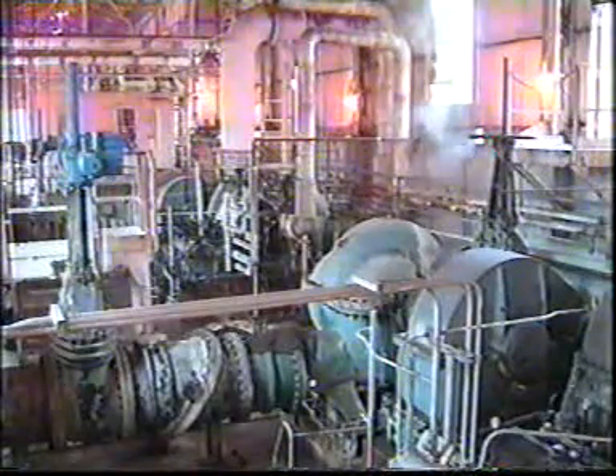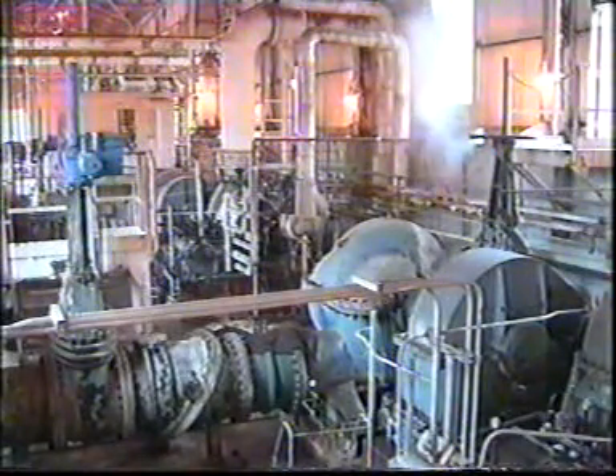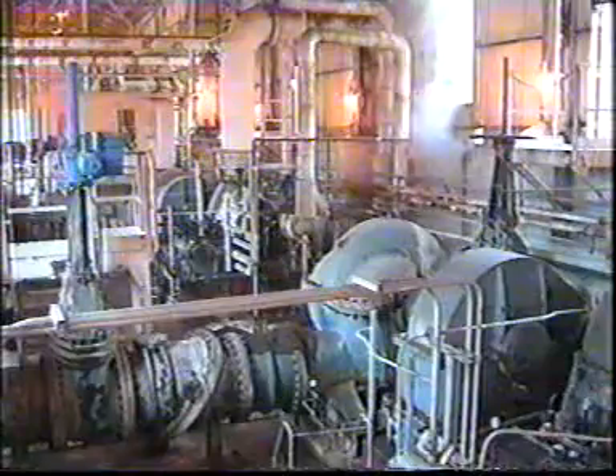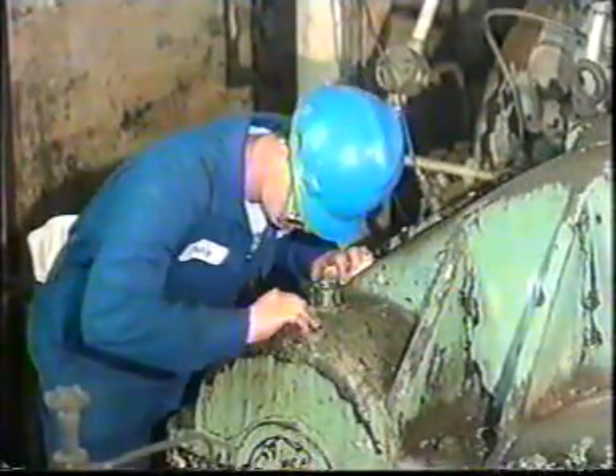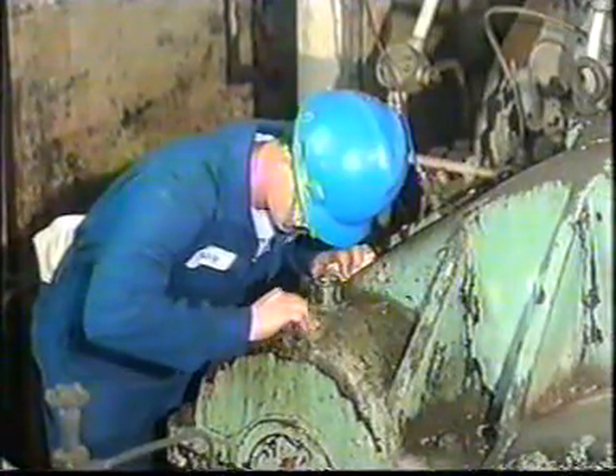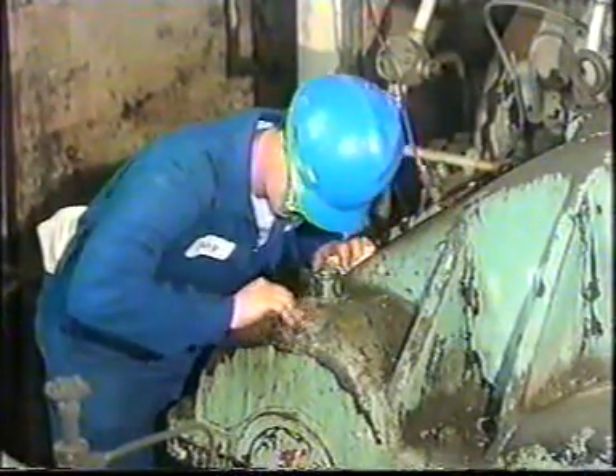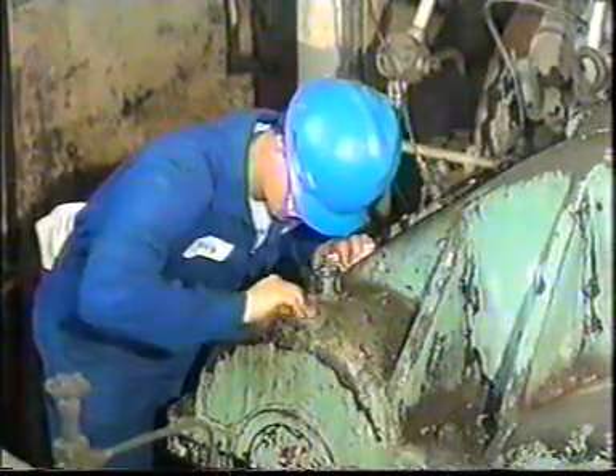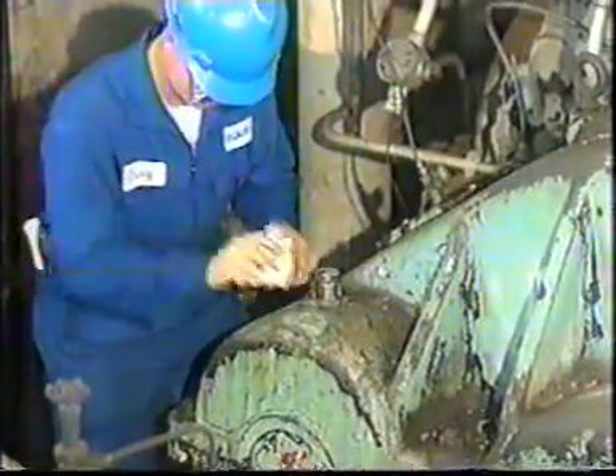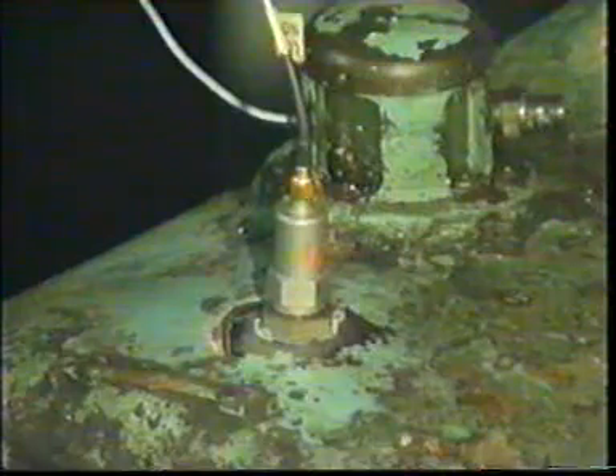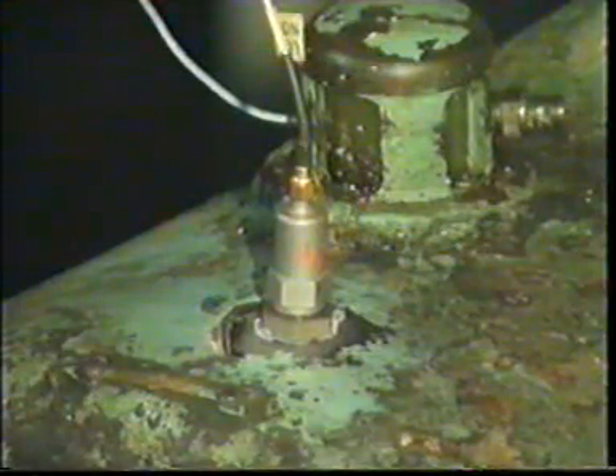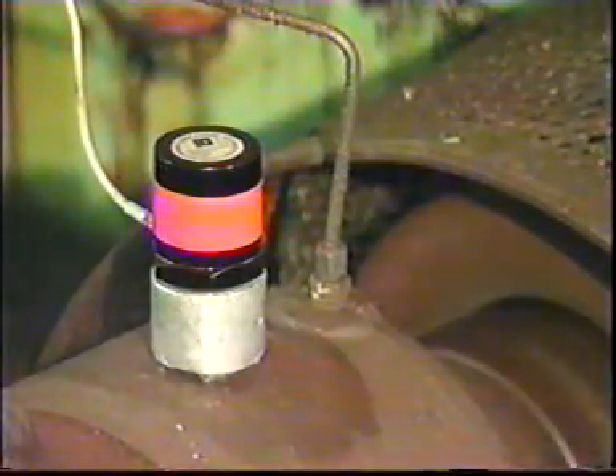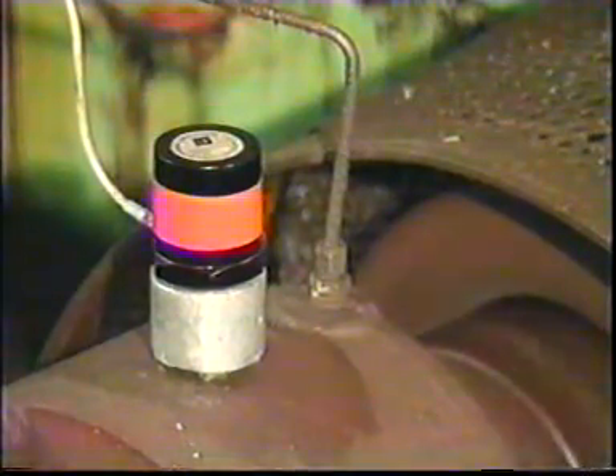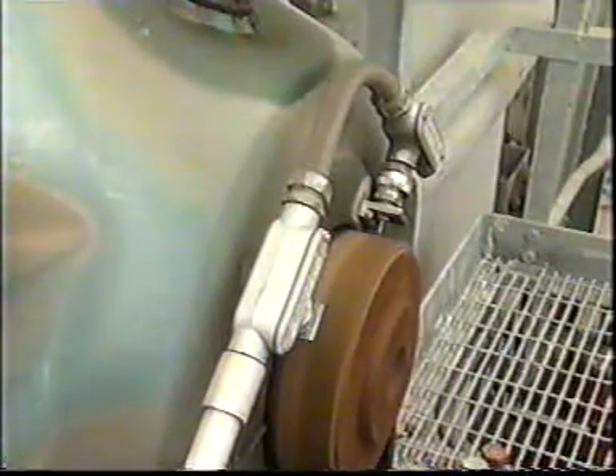Make sure environmental conditions won't exceed the probe specifications. Most probes have a temperature limit. Mounting methods and surface preparation determine the range and response for the sensor. Response decreases with the amount of contact area's roughness and roundness. Velocity and acceleration sensors need to be mounted to a machine's surface to keep them from losing contact with the machine. There are several methods for mounting a sensor to a machine.